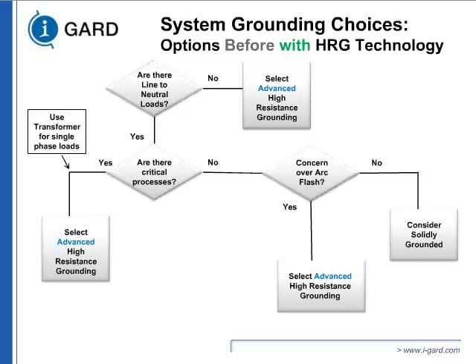You take the second fault out. When you do a risk analysis, you can tell your management that if the first ground fault is 90 to 98% and I don't have a ground fault, I have a second fault priority system, what is the probability I'll have two faults at the same time? It is there, but it's very low. So you can see HRG, high-resistance grounding technology, is an option. You can use it. We have used it successfully since 1960 up to 5,000 volts without any problem. In one of our international plants, we use it up to 6,900 volts.